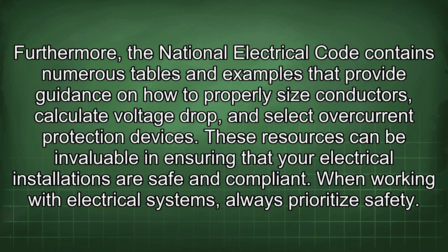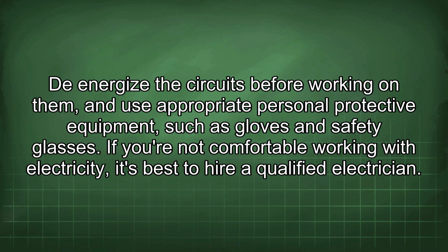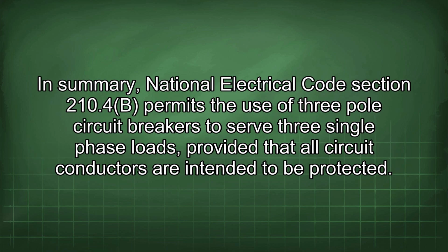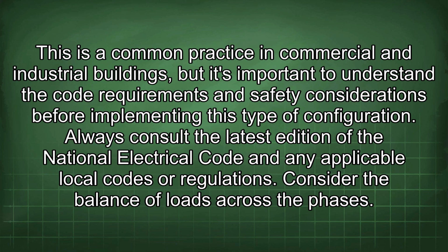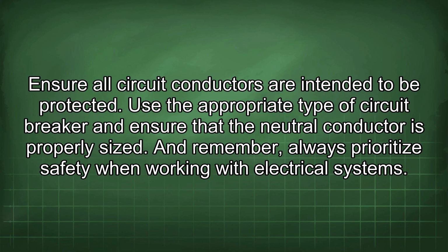When working with electrical systems, always prioritize safety. De-energize the circuits before working on them, and use appropriate personal protective equipment such as gloves and safety glasses. If you are not comfortable working with electricity, it's best to hire a qualified electrician. In summary, National Electrical Code Section 210.4(B) permits the use of three-pole circuit breakers to serve three single-phase loads, provided that all circuit conductors are intended to be protected. This is a common practice in commercial and industrial buildings, but it's important to understand the code requirements and safety considerations before implementing this type of configuration. Always consult the latest edition of the National Electrical Code and any applicable local codes or regulations. Consider the balance of loads across the phases. Ensure all circuit conductors are intended to be protected. Use the appropriate type of circuit breaker and ensure that the neutral conductor is properly sized. And remember, always prioritize safety when working with electrical systems.